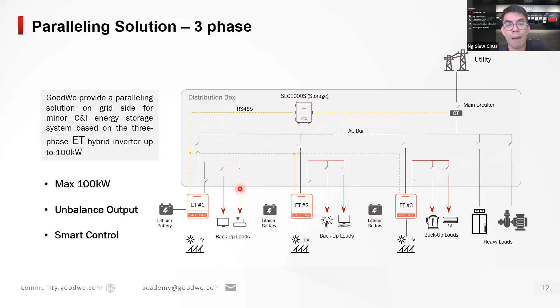Our system also supports customers who would like to use a single phase inverter, for example the ES series or EH series, connected to a three-phase system. That's possible, but you need a smart meter that has three-phase. We read the incoming power purchased from the grid and command the hybrid inverter to feed the same amount of power into a single phase, achieving a virtual net zero: outputting more power into one phase to offset the purchased power from the other two phases. This depends on whether your country allows it, but technically our system does support this feature.